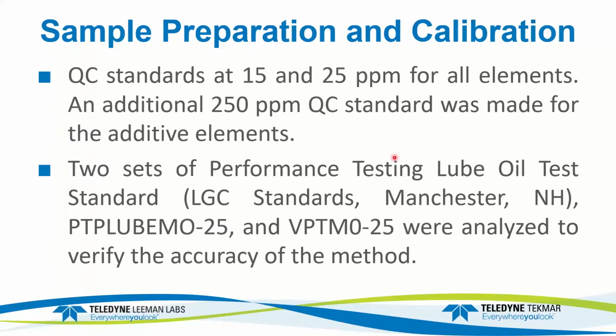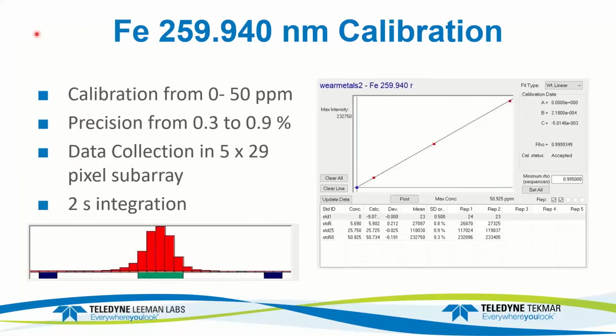We also prepared some QC standards at 15 and 25 ppm for all elements, and a higher one for the additive elements. We really monitored the 25 ppm the most. We did that every 12 samples, so we ran that roughly 10 times during the analysis. The QC demonstrates what the stability is. And then for accuracy, there are performance testing oils also available from LGC Standards for all the elements done by the wear metal technique, as well as the additive elements. We prepared those and ran those after the calibration and check standards passed. We went ahead and ran these certified standards.